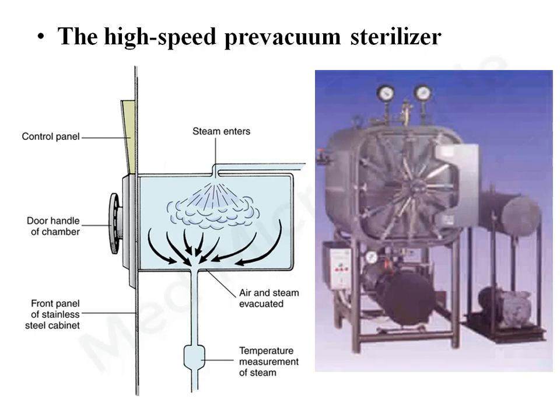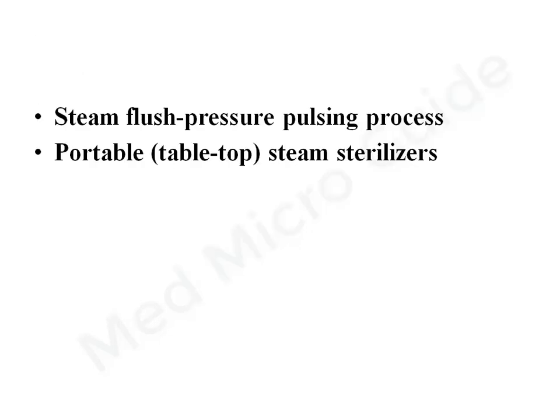The pre-vacuum sterilizer is similar to gravity displacement except it is fitted with a vacuum pump. The vacuum sucks all air from porous loads and enables instantaneous steam penetration. It typically works at 132 to 134 degrees Celsius at 30 psi for 3 to 4 minutes. In steam flush pressure pulsing autoclave, air is removed rapidly by repeated alternating steam flush and pressure pulses, almost as efficient as pre-vacuum sterilization. Portable or tabletop sterilizers are used for small instruments like hypodermic syringes, needles, and dental instruments in outpatient, dental, and rural clinics.